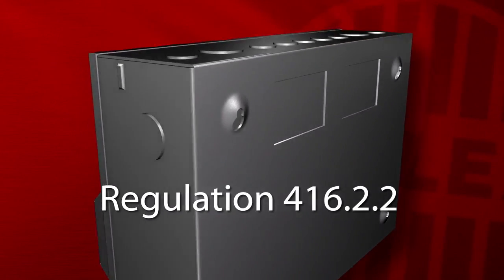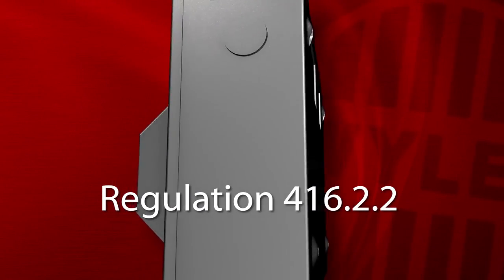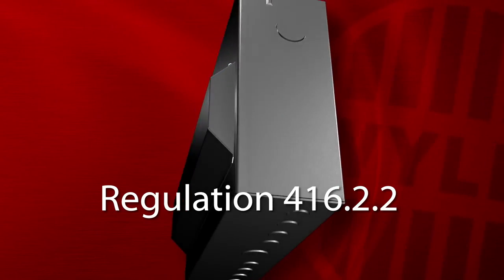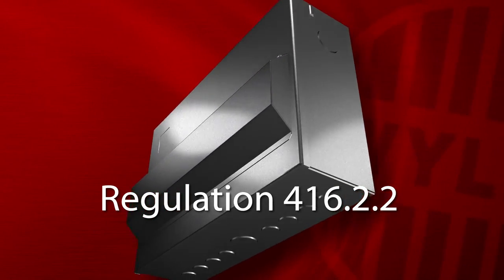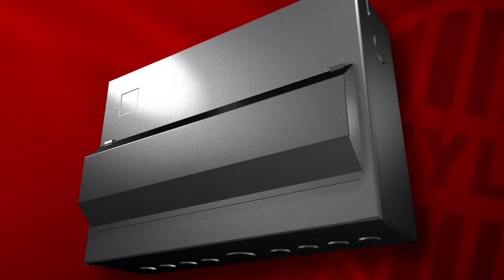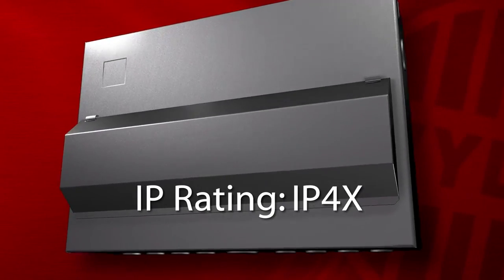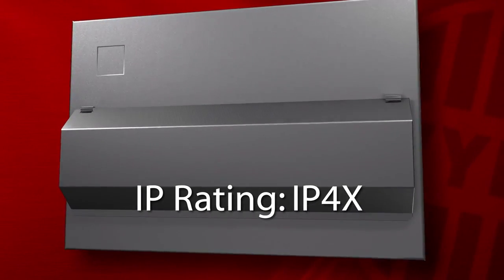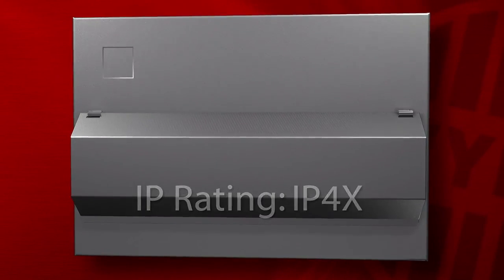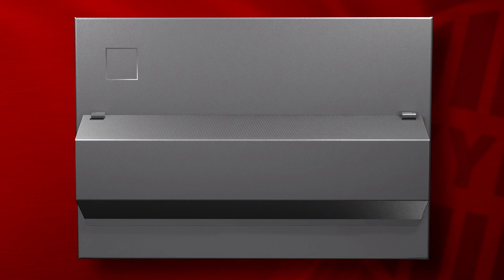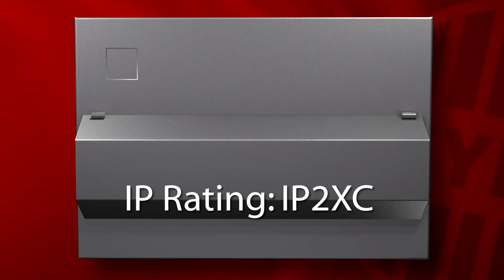Regulation 416.2.2 of the wiring regulations also requires the installer to ensure that the consumer unit, when fully installed, achieves an IP rating of IP4X on the top elevation, if this is readily accessible, and elsewhere on the consumer unit, the other elevations of the enclosure must be to IP2XC.